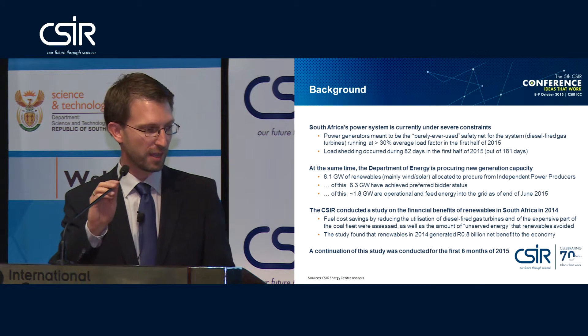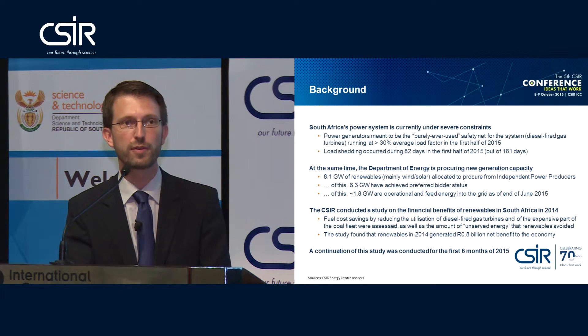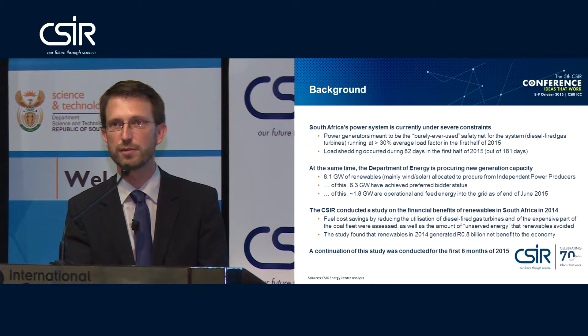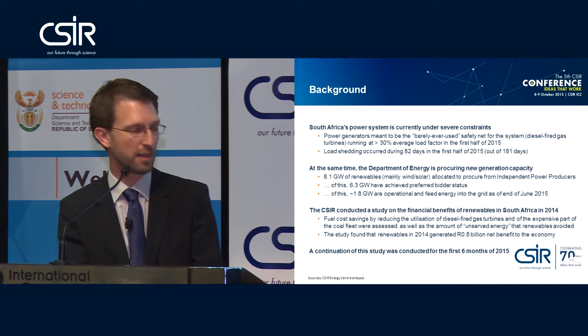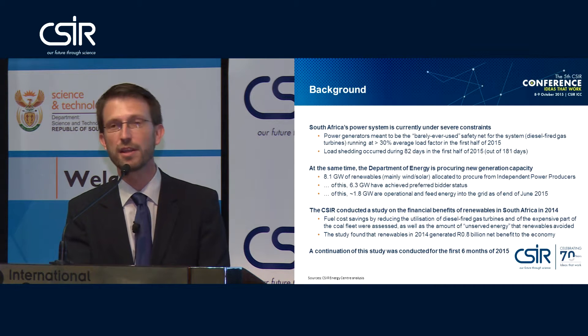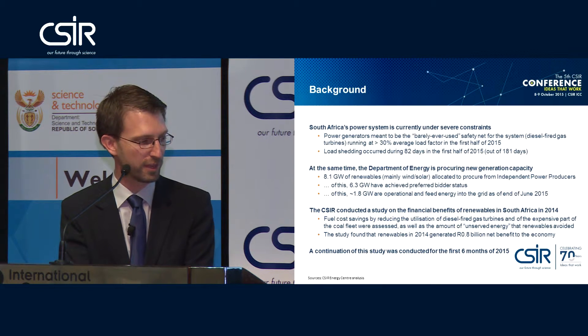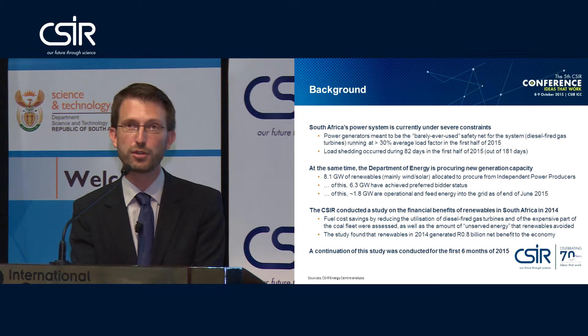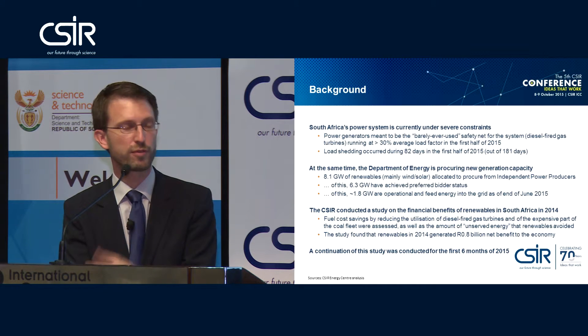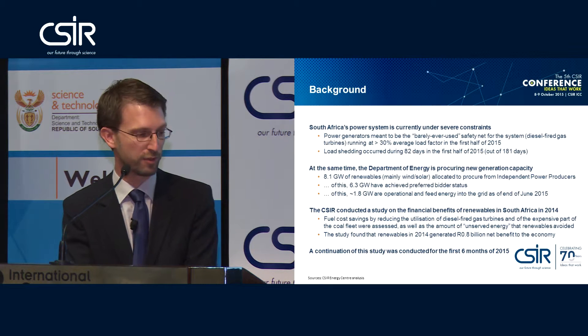A little bit of background. The South African power system is under severe constraints at the moment. We have power generators that are designed to be the safety net for the system — gas turbines fired with diesel — that ran in the first half of 2015 at roughly more than 30% average load factor. They are designed for 3 to 4%. So that is a good quantitative indication of the constraint of the system. We had load shedding on 82 days in the first six months of 2015 — almost every second day.